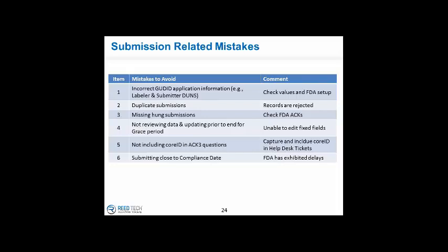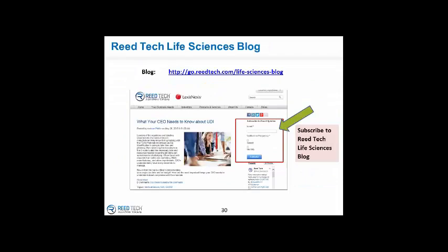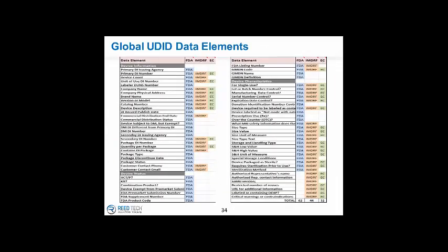And there's a list of a number of fields, and actually the slide, let me go quickly down to that. You'll see that the blue column here is the FDA list, and the second column in orange is what's recommended by the IMDRF. Lo and behold, the FDA did not conform, so they had a bunch of extra fields. And what we see from the EC is some conformance, and yet they have their own dedicated fields in some cases. So bottom line, there's a common core set.